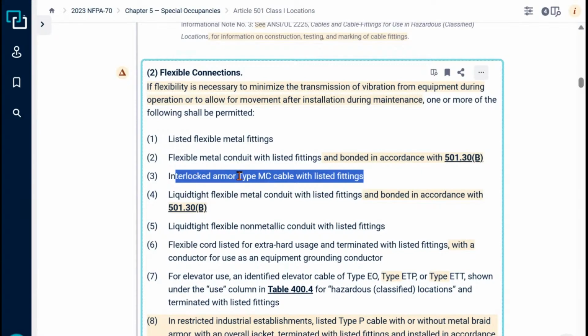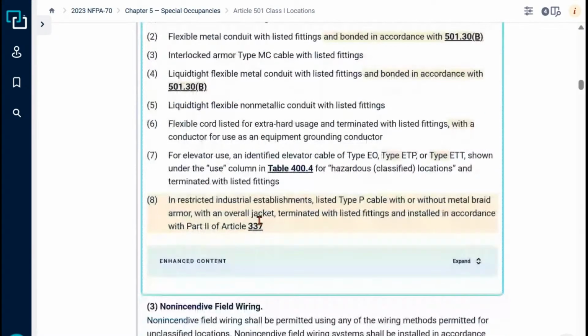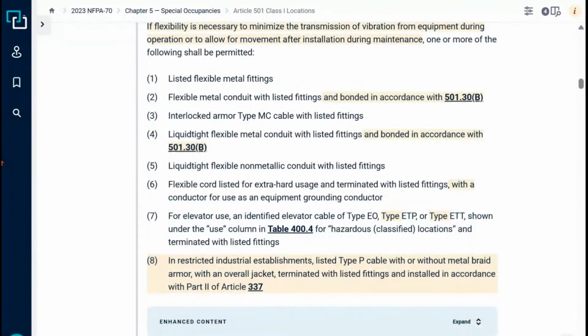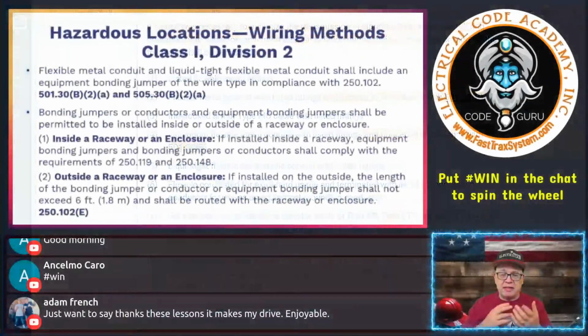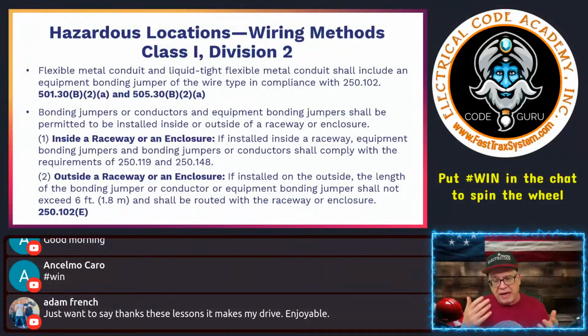That's going to allow flexibility. I guess the point is, depending on the different type of application that you're dealing with, you've got some allowances, and it's important for you to know whether you're in a Class 1 Division 1, because you have very limited uses of the different wiring methods. Whereas if you're in a Class 1 Division 2, it opens it up greatly.